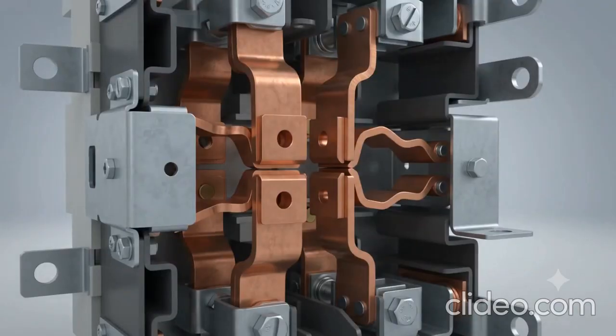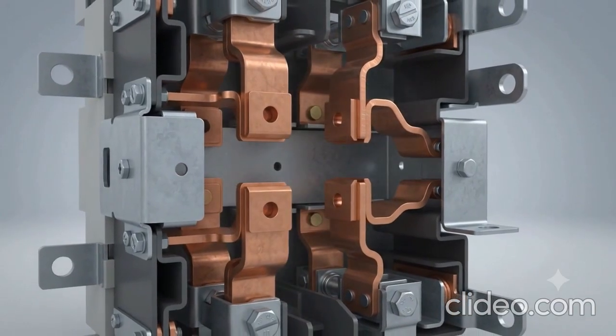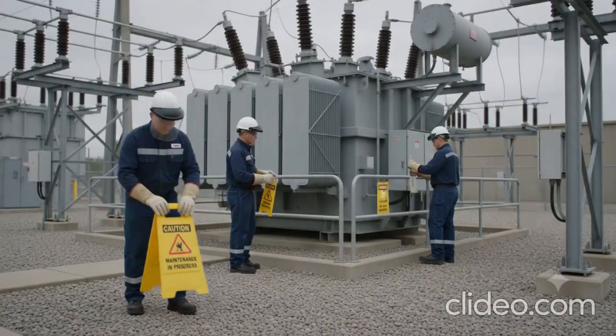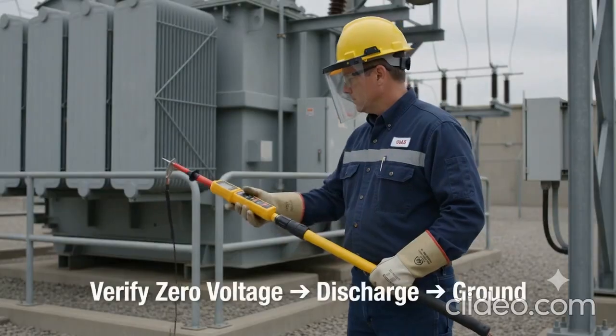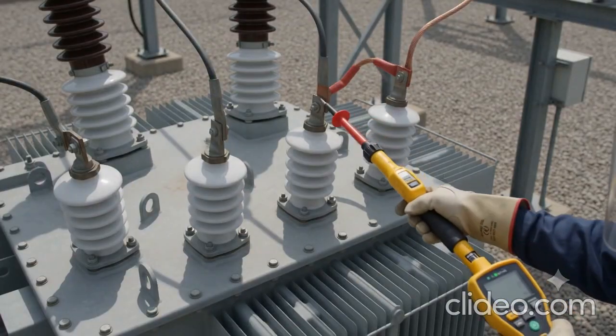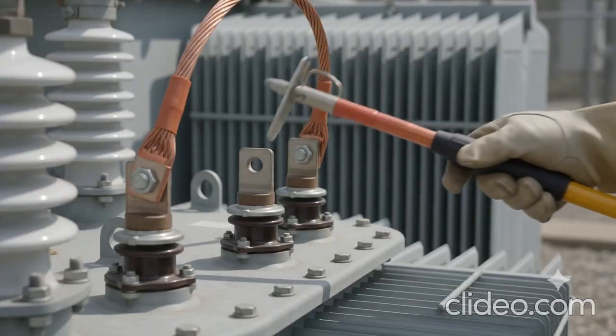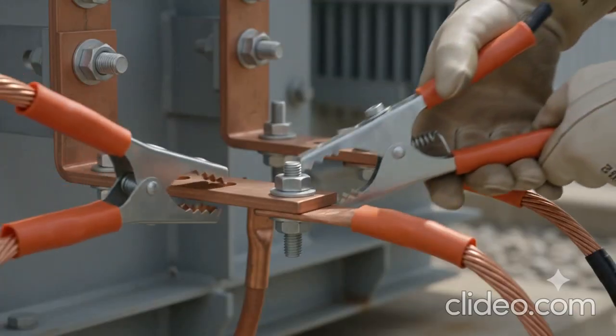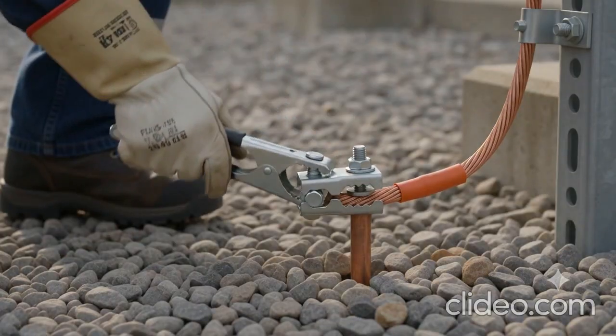Circuit breakers and isolators are opened. Lockout-tagout procedures are applied. Appropriate warning signs are installed. After isolation, the absence of voltage is verified using approved test equipment. The transformer is then properly discharged and grounded before maintenance begins.